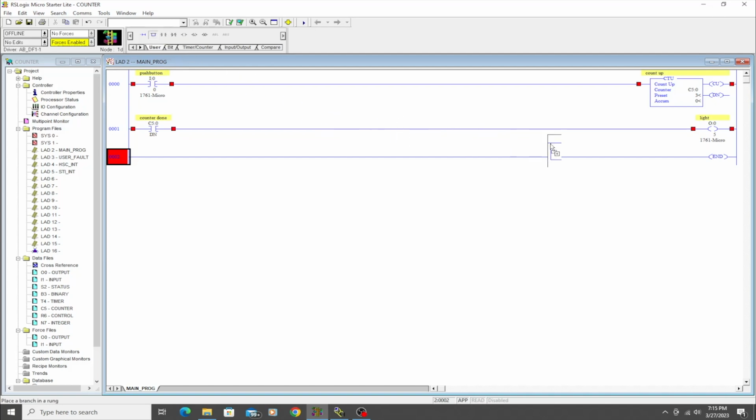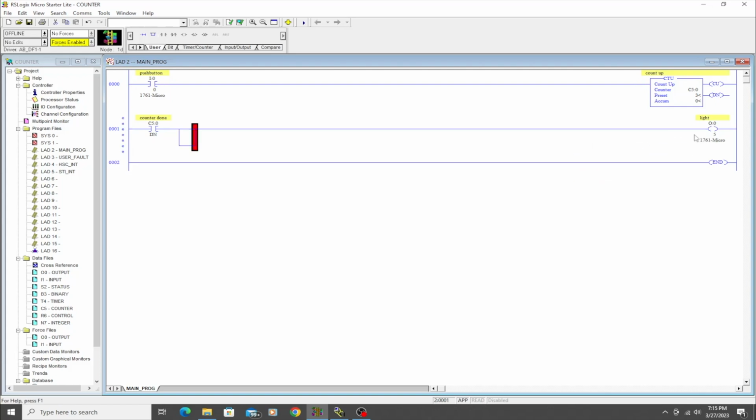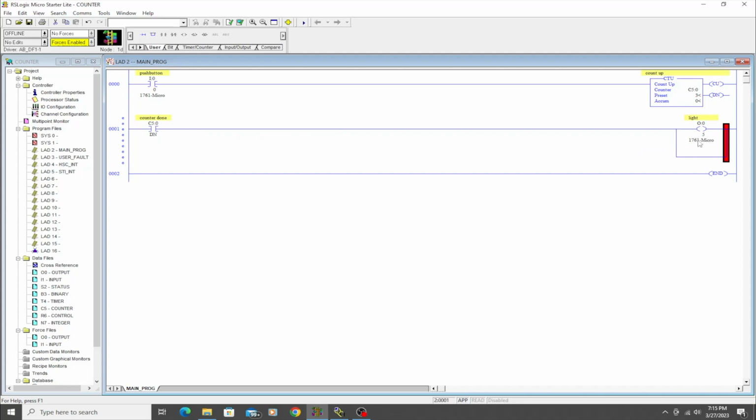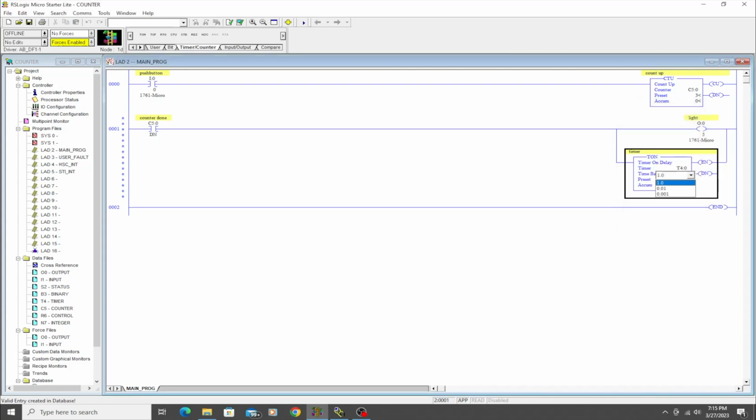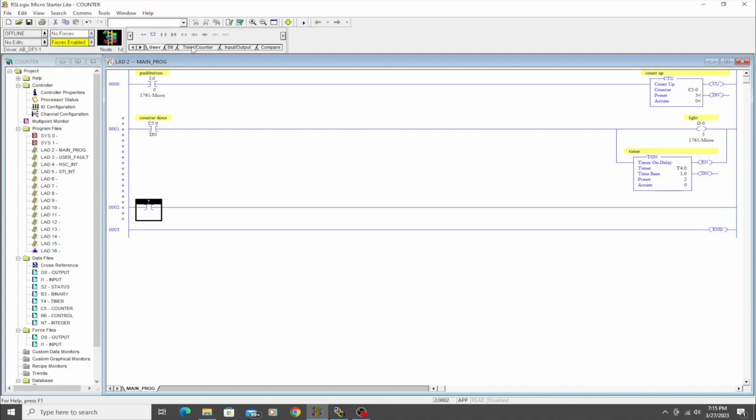So I'm going to drag this rung branch over here. We're going to put it there, and I'm going to drag it over, and I'm going to branch around this output. What this is going to allow me to do is I can put another instruction right here, and I'm going to put a timer, and we're going to address this T4:0. Just put timer, do 2 seconds.